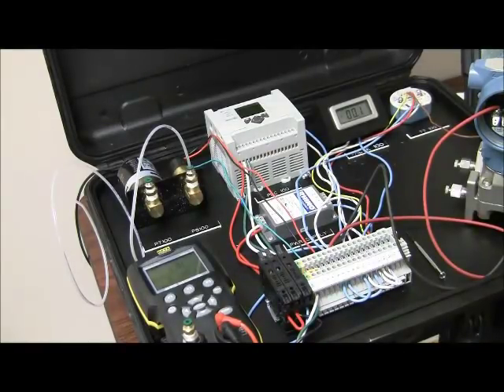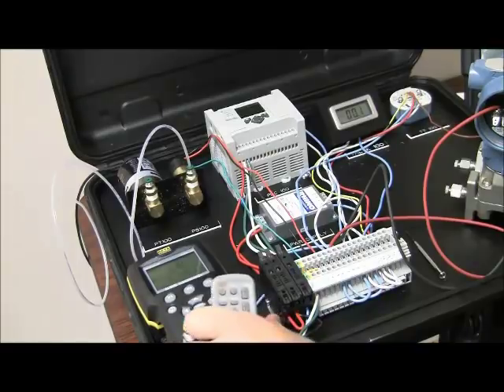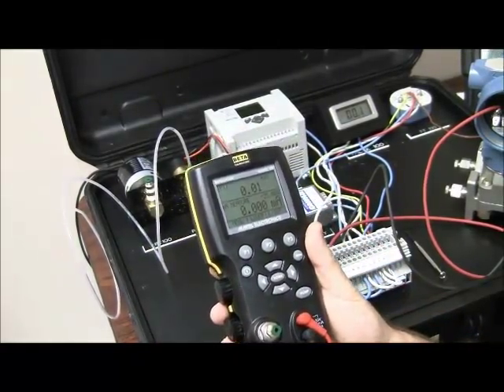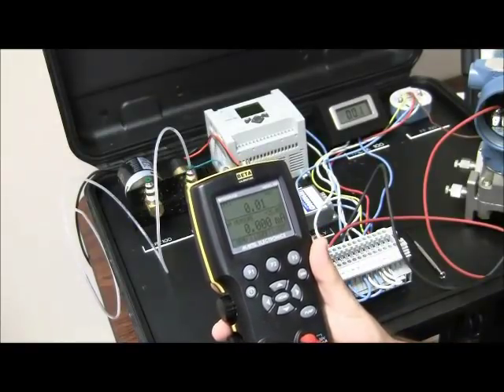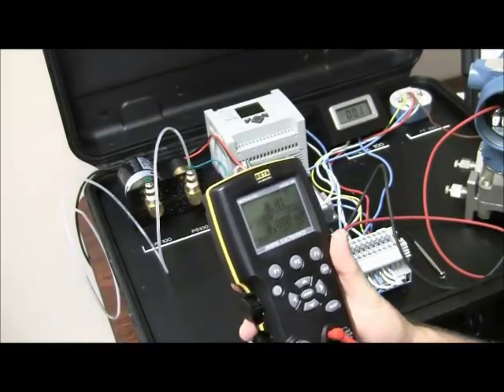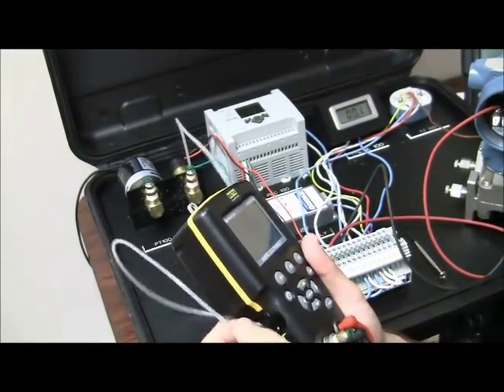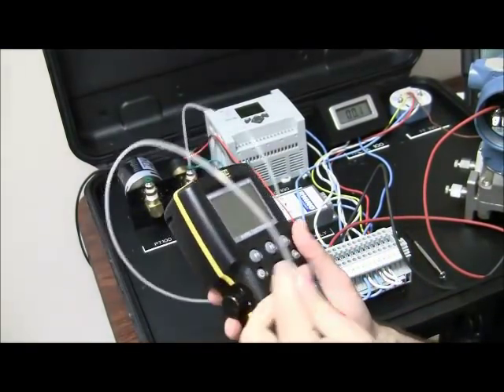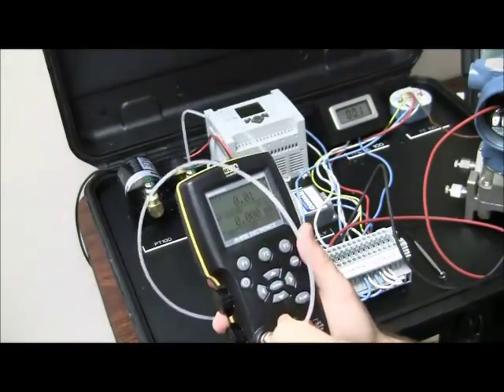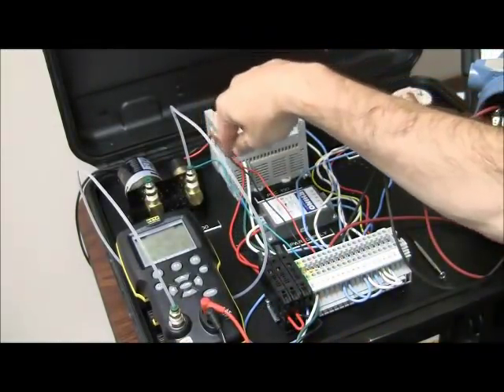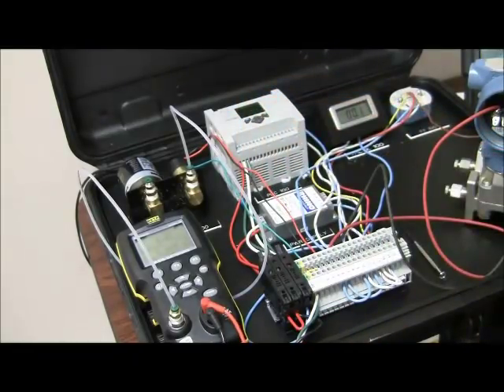So let's get started here. We're going to be working with the Beta Gauge 330, 0 to 150 psi electric to do our test today. So the first thing I'm going to do is make my connections here. I already have the pressure line already hooked up here. So I'm just going to run this into my 330 here, the switch. Now the switch is wired, it comes in here to the terminal block.